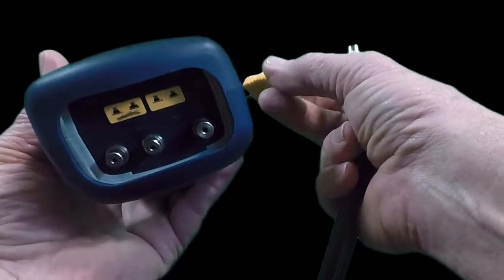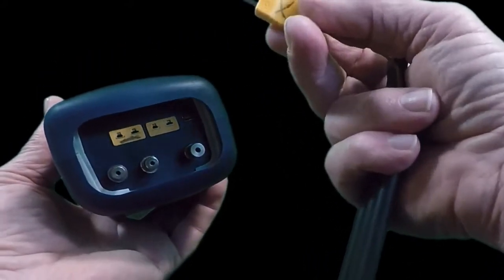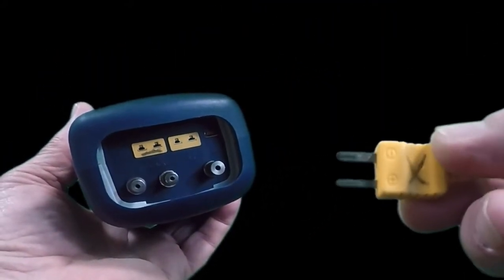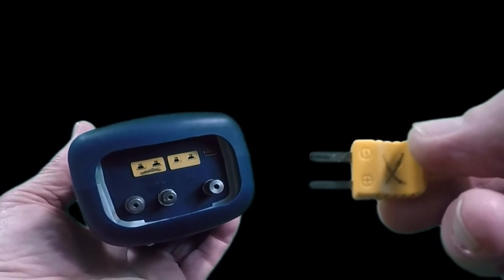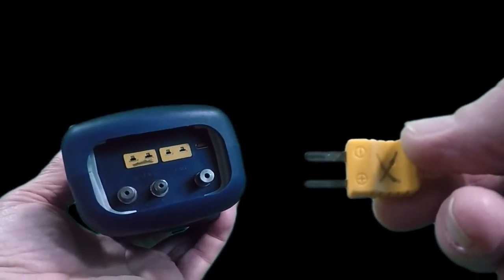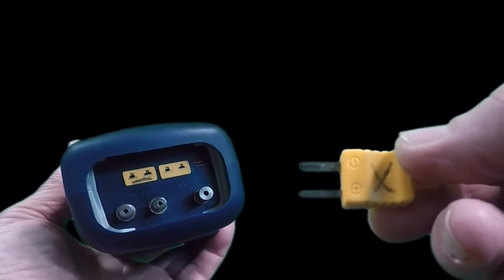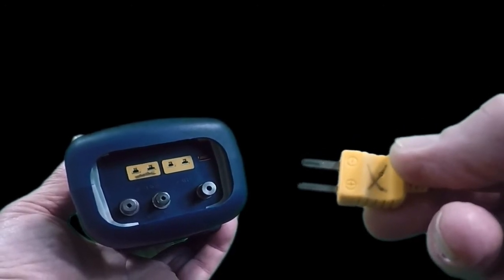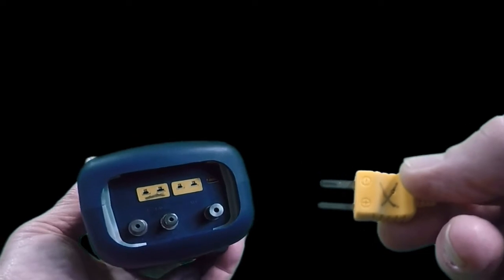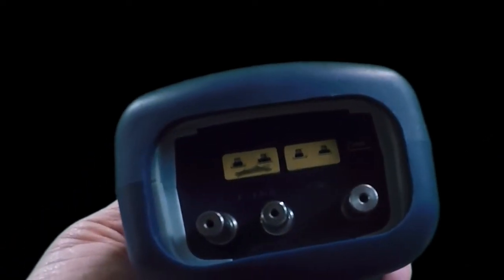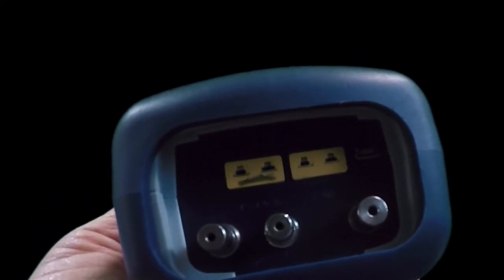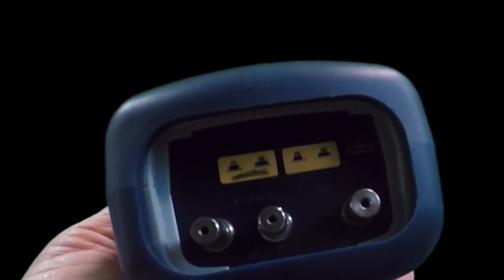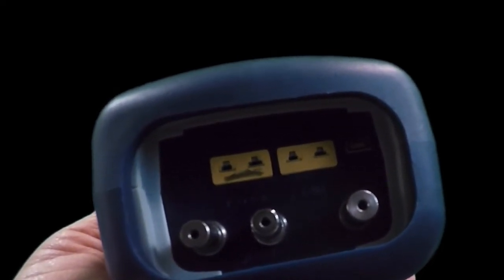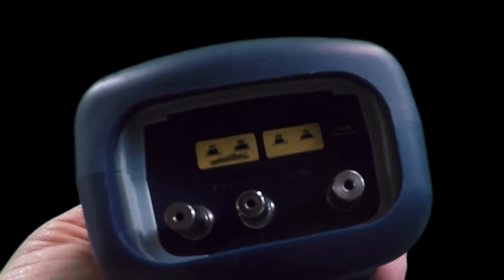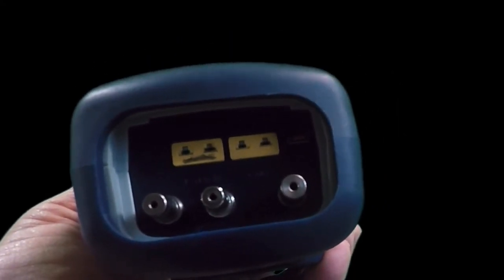Like I mentioned before, it is a K-type thermocouple. If you look at the two blades on a K-type thermocouple, they're different widths. The wider blade goes in on the right-hand side. Just to make it easier to plug it in, I put an X on the top of the thermocouple. That corresponds with the left-hand port. You also notice on the thermocouple ports in there, I put a little Sharpie mark across the one on the left-hand side, just to make sure that I plug it into the right thermocouple port. So we'll go ahead and plug that in.